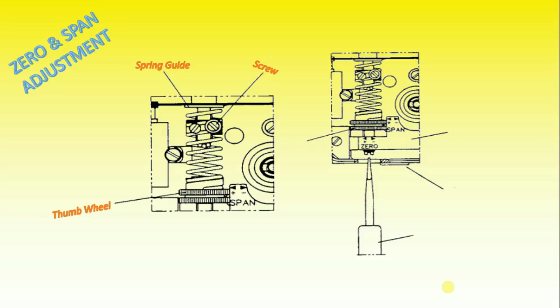Always check zero after adjusting span. Zero is adjusted by turning the silver lower thumb wheel located on the lower arm, or externally with a screwdriver through the zero adjustment opening. Remember to install the cover to ensure the unit's sealing.